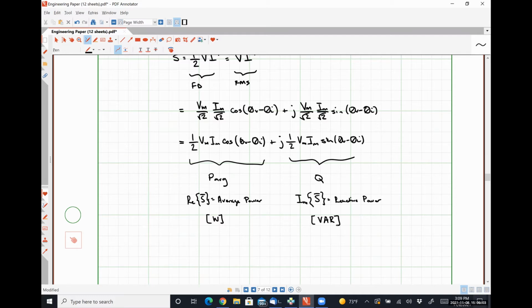Some of the loads we deal with on an everyday basis absorb reactive power, like induction motors, which are a classical absorber of reactive power. For example, if we tried to turn on every one of those heat guns in the room at the same time, I'd be willing to bet we'd throw at least one breaker if we did it, okay?